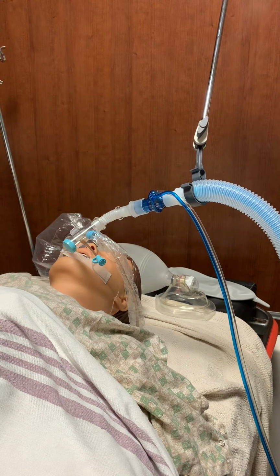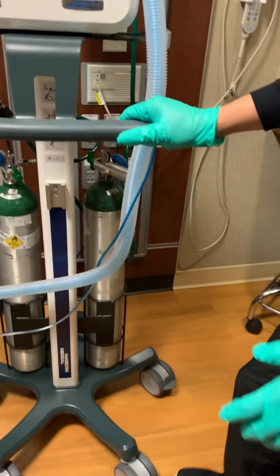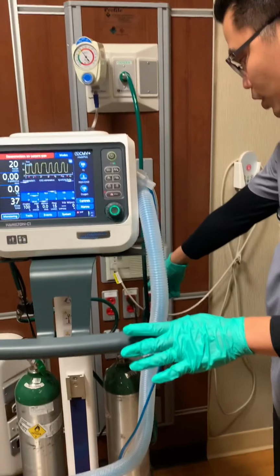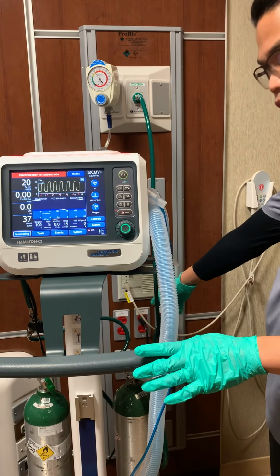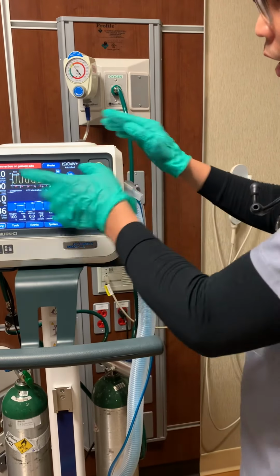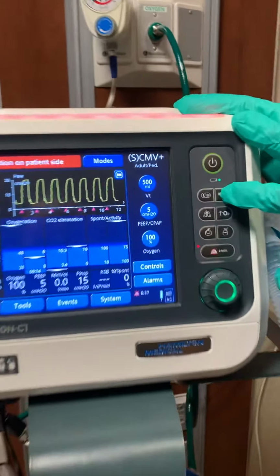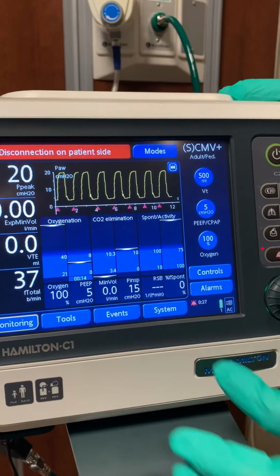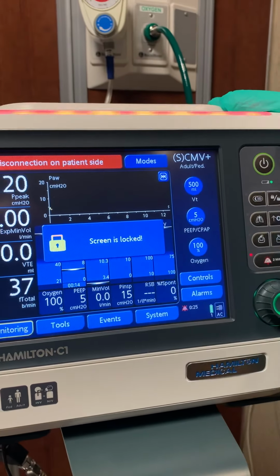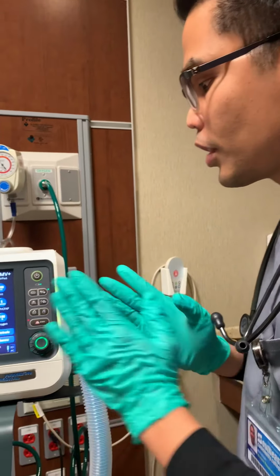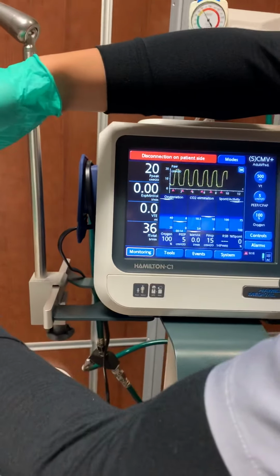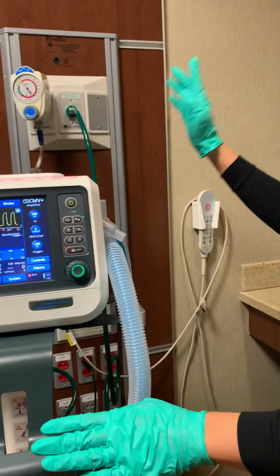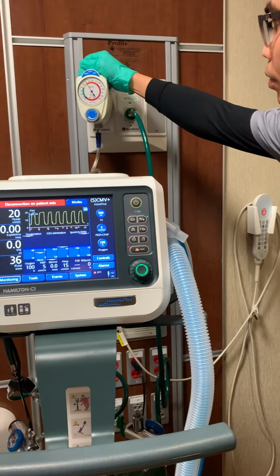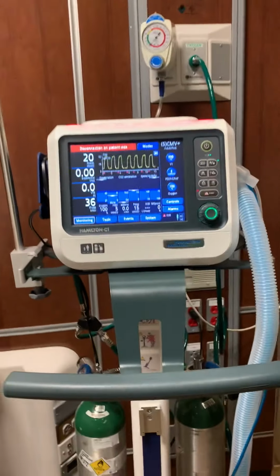So inspect everything, make sure this one is secured and locked, and then check if the connector is hooked up on the red outlet. And then on the ventilator side, make sure we screen lock it. The reason why we screen lock it is that we prevent any persons from inappropriately pressing these settings, for safety purposes. Make sure this one is secured at all times so that this will not fall down on the patient's head. And then double check everything, the suction, turn it off. And then make sure everything is secured.